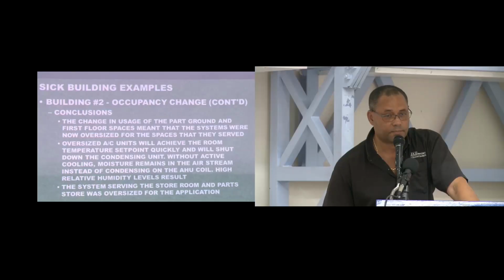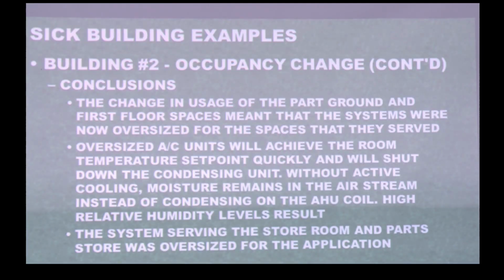On the ground floor, the same size system that was used for the offices was servicing a storeroom and a spare parts room. Absolutely no load. So that started off wrong in the first place. The system was way too big, no windows, nothing, because it was secure. It was just a tight box, nobody in it, no lights on because it's just parts, absolutely no load. So they were just making their situation worse on that floor.